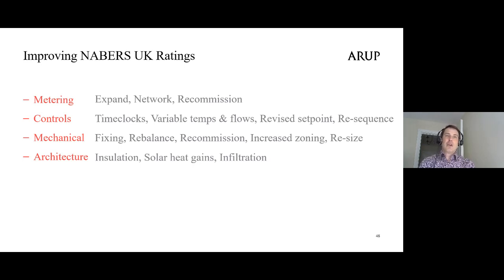The first thing, also touched on by Karina, is metering. Part L and BREEAM have really pushed sub-metering well, and most modern buildings have a lot of it, but until recently there's been poor incentive to use it. I've had an ex-BMS engineer tell me that facing practical completion on a new building, his boss instructed him not to commission the metering because nobody cared. Similarly, we recently went into a client building with extensive sub-metering, but it went back to a computer in a facilities management room that wasn't available remotely and was barely used, let alone used to identify how the building was performing or find opportunities to tune it up.